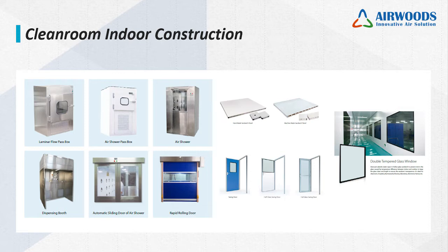For the partition wall and the ceiling, we use color-coated sandwich panels. Normally there are three options for the core material: glass magnesium, PU, and local rock wool. PU is, of course, the best but with a high price, and rock wool has the best fireproof performance. But we always recommend glass magnesium sandwich panels because they have excellent performance in fireproofing, waterproofing, and insulation. For most projects, 50 millimeter thickness is enough, while some projects ask for 100 millimeter thickness.